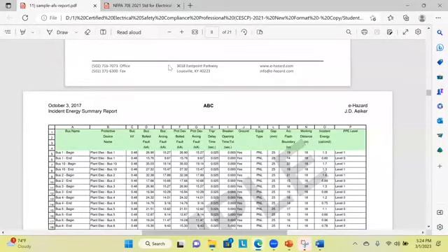So here in this report, you can see that there is a plant with bus number 1. At this voltage level, the voltage is 480 volts, 0.48 kV written here, and the incident energy is 0.80. So that means for this location, the arc flash hazard does not exist. The arc flash boundary will not be there, but the 480 volts is there. So the shock protection boundary will be developed.